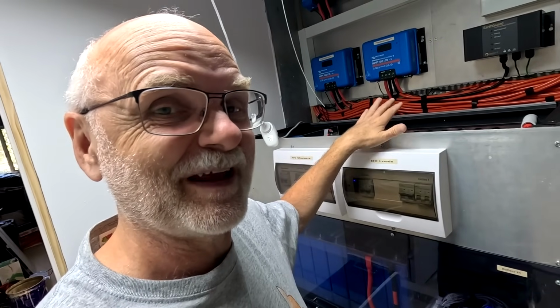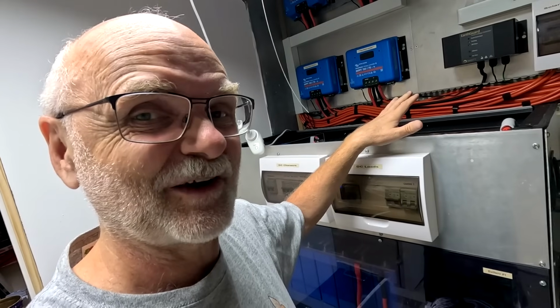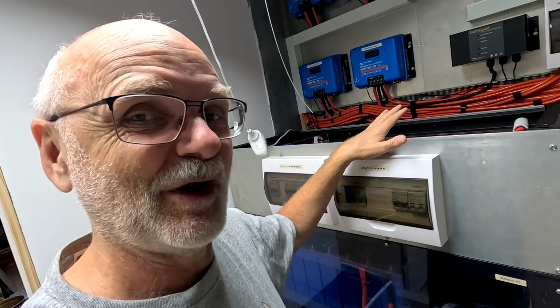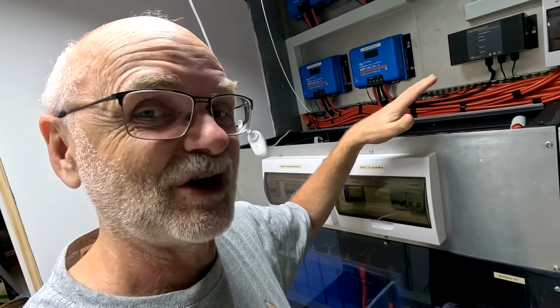So all the batteries need to be on one side of the shunt and everything else is on the other side of the shunt. So you're actually measuring what is going into the batteries and out of the batteries to determine the correct state of charge. If the batteries are connected on the other side of the shunt, they're getting charged from the inverter and discharged from the load without the Smart Shunt knowing about it.